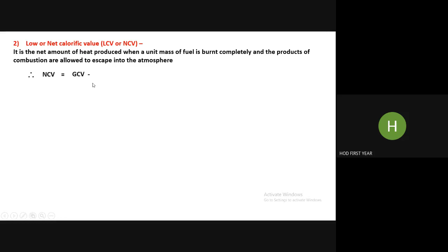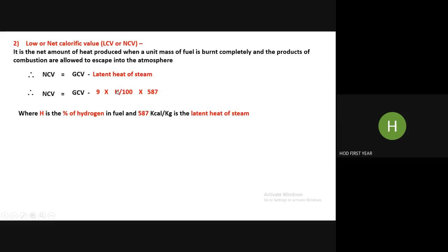Accordingly, GCV minus the latent heat of steam can be written as 9 into H by 100 into 587, where H is the percentage of hydrogen. हायड्रोजनचं पर्सेंटेज जे काय आहे त्या फ्यूल मधलं, दॅट इज एच, in the fuel, and 587 kilocalorie per kilogram is the theoretical latent heat of steam. So that is subtracted from the GCV value, and we get the net or practical calorific value. So net calorific value is equal to gross calorific value minus 9 into hydrogen percentage in that fuel divided by 100 into 587 kilocalories per kilogram.